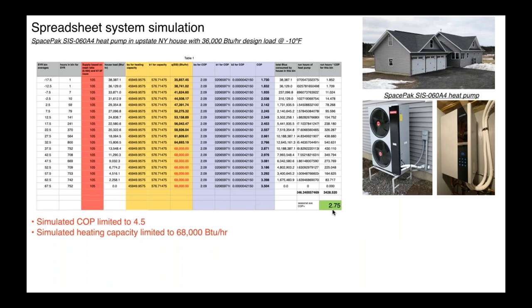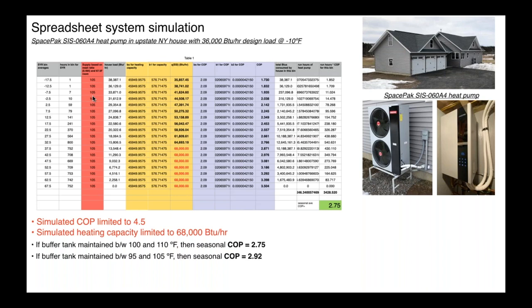Well, you might say, how come this is lower than that Boston project? Well, because look at what we're doing with water temperature. We're maintaining it in this particular model at 105. And I'm sure most of you are thinking, well, what if we lowered that water temperature? All right, well, I'm going to lower it just 5 degrees. Really simple. Instead of 105 in this column, it's going to be 100. Imagine we could turn the heat pump on at 95, turn it off at 105. Look at what our COP does. It goes from 2.7 to 2.9. That's only a 5-degree drop in the water temperature.